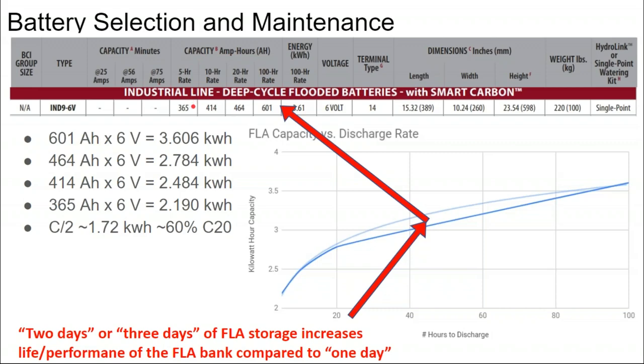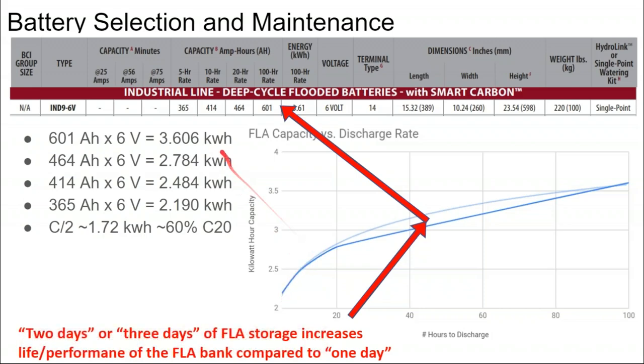And so the danger with lead acid is you've got this pretty sharp drop-off. Once you start getting under - they don't even give you a rating for a 2 hour discharge - they pretty much say once you get under a 5 hour discharge rate and start exceeding that, you're not going to get any power at all out of your battery.